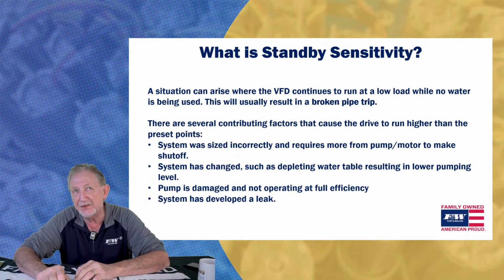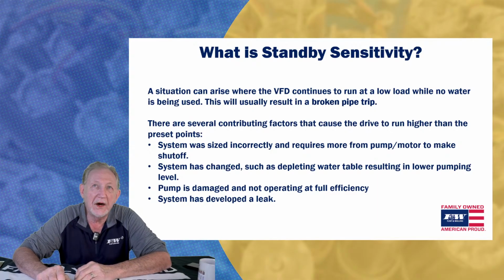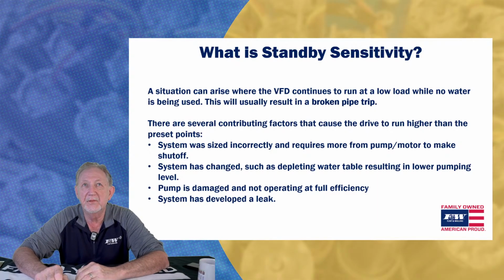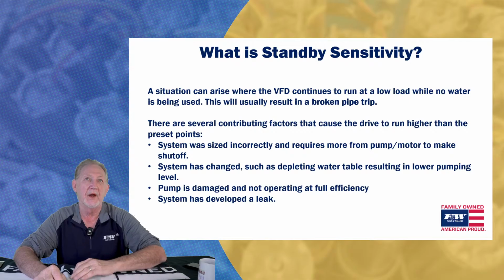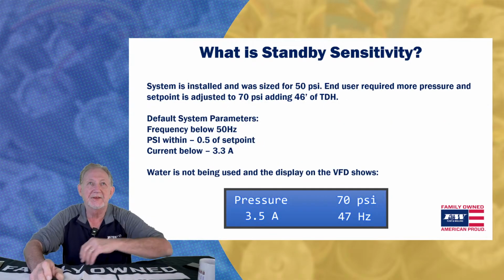If the system's changed, such as the water table's lowered, resulting in a lower pumping level. If the pump's damaged or not operating at full efficiency, that happens sometimes when you try to take a conventional system and upgrade it, or the system has developed a leak.